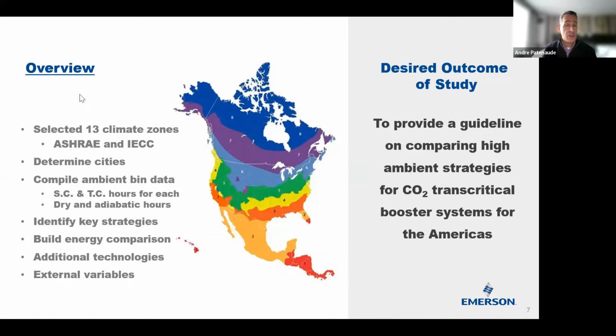Then we looked at what strategies we really wanted to compare against. We took the most common high ambient strategies, and I'll review those in a minute. We built an energy comparison using the EES software. The system size we chose was 400,000 BTU medium temp at +18 saturated suction, and 100,000 BTU low temp at -20. That's very close to the total cost of ownership capacities I showed you earlier, so that gives you an idea of the size of the supermarket.